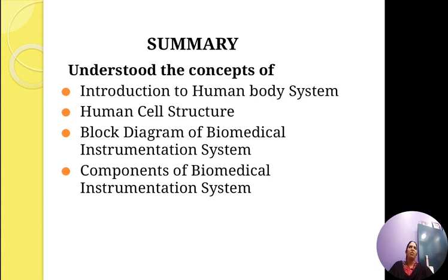The source of the measurand is the human body, which generates a variety of signals, called biosignals. Then the transducer or the sensor is a device which converts one form of energy into an electrical form. Then we have the signal conditioner, which converts the output of the transducer into an electrical signal quantity suitable for operation of the display or the recording system. The signal conditioning most commonly used is either amplification or filtration or A to D conversion or D to A conversion, depending upon the requirement.